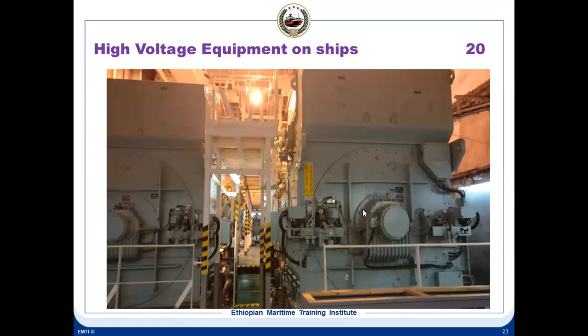In the case of this generator, the permanent magnet generator output is an AC output which is connected to the AVR. So the AVR has a constant supply which is not disturbed by the load variations or anything. It is constantly given to the AVR from the PMG. The PMG, permanent magnet generator, is on the same shaft which is driven by the engine. So these are for the lubrication, lubricating pumps. This generator is not an air-cooled generator, it's a water-cooled one.